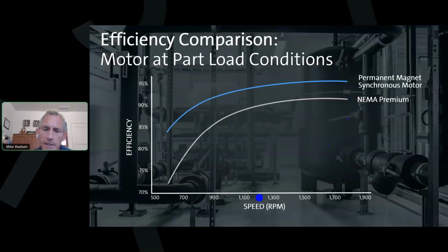What we're looking at on this slide is motor efficiency curves. The bottom one is a 10 horsepower NEMA premium, and the top one is a IE5 ECM permanent magnet motor, 10 horsepower. Here's motor speed on the x-axis. Here's efficiency on the y-axis. This is a 4-pole motor, so my max speed is 1850 RPM. So we can see here at full speed, we're saving maybe that 7% energy savings. We're more efficient by 7%.